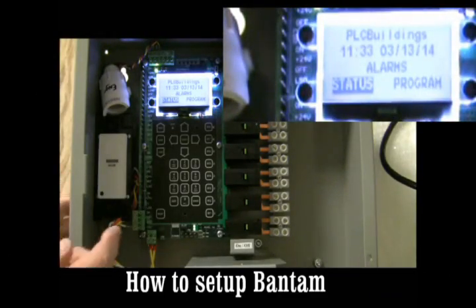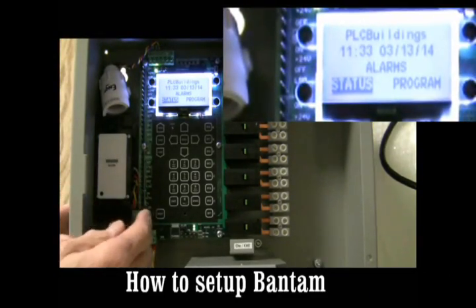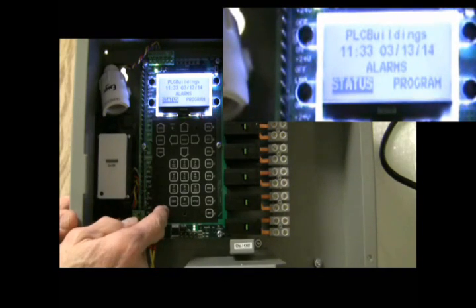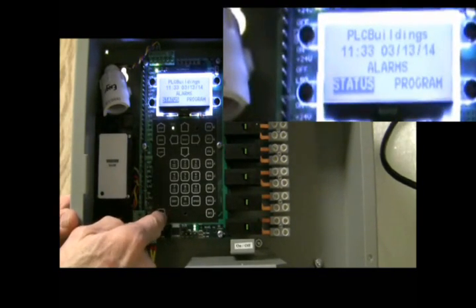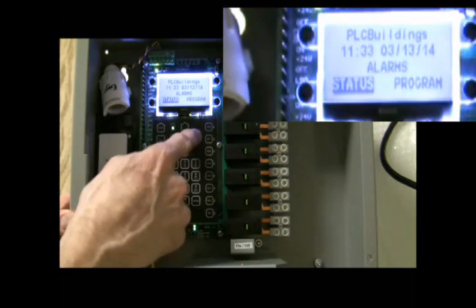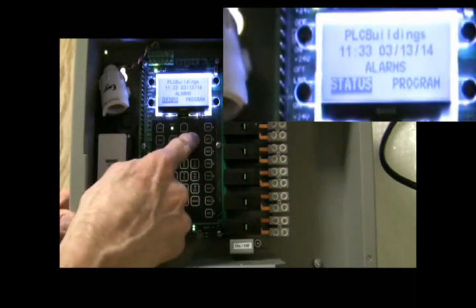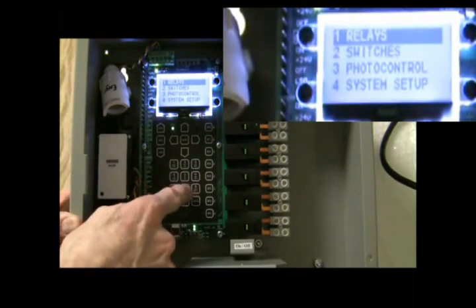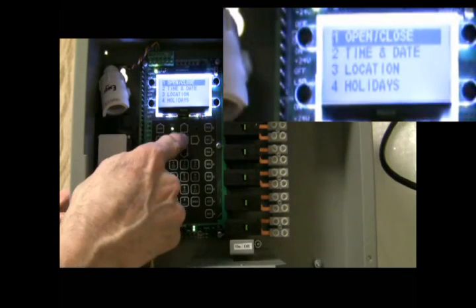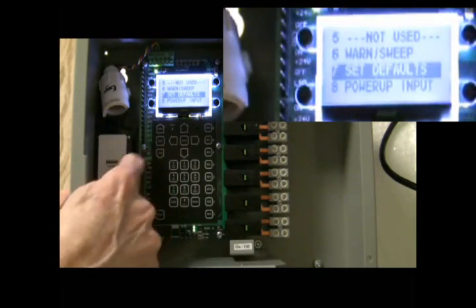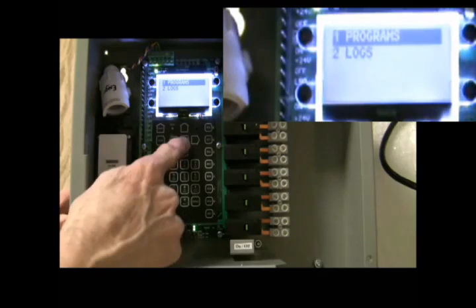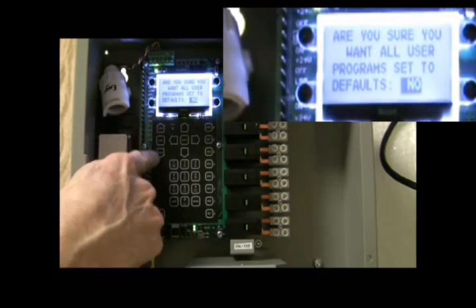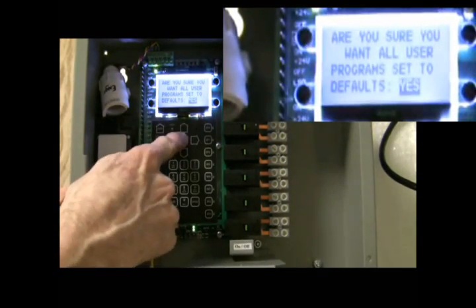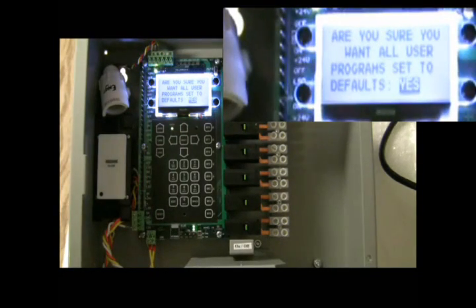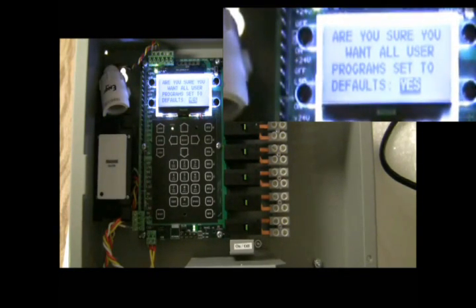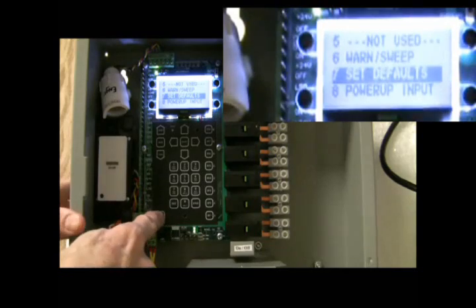Okay, this video explains how to set up a Bantam out of the box. The first thing you want to do is ensure there's no program, so you want to clear all the memory. So you press back and forth. You want to go to program, system setup, raise up to set defaults, select program, raise or lower to say yes, select. This will clear all the memory. You'll start from scratch. Press the reset button.